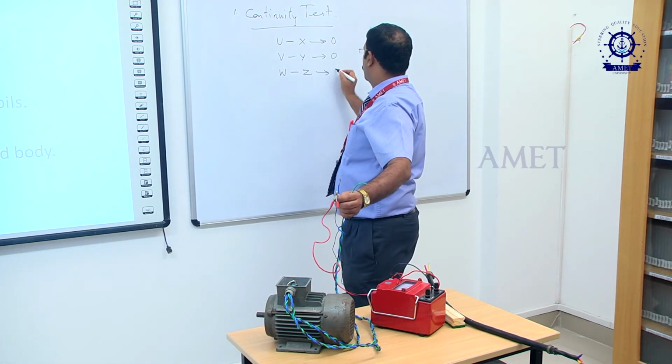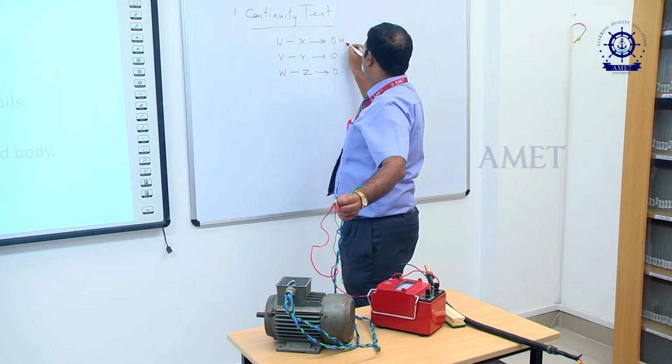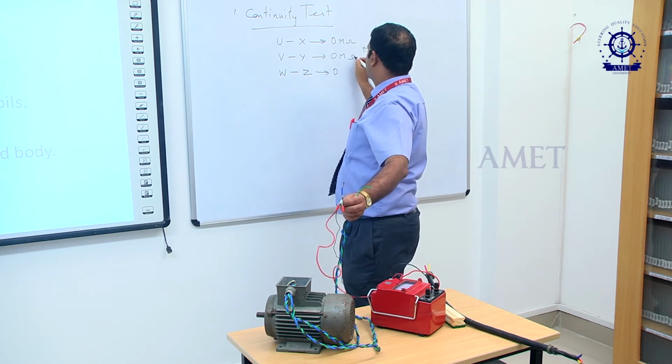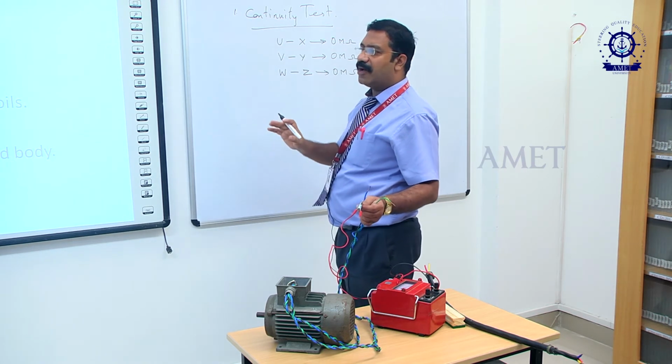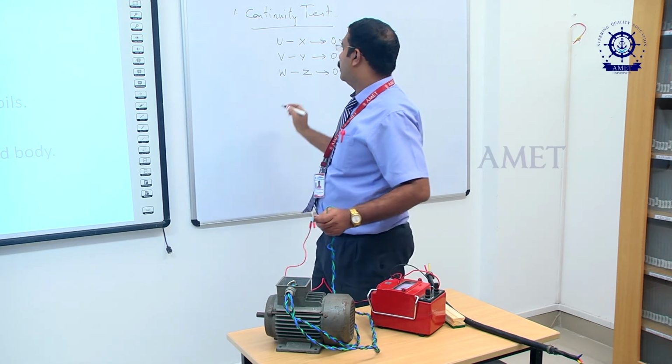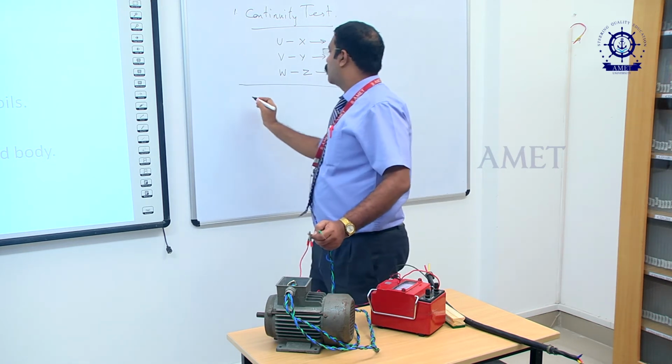This tells us that the R phase, Y phase and B phase have good continuity. Therefore the first test is over.